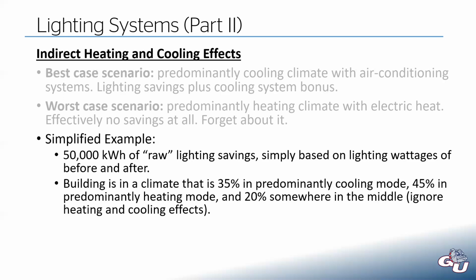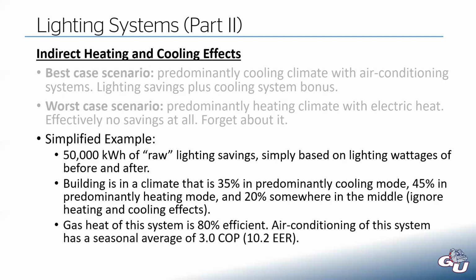And let's say this building is in a mixed climate where 35% of the time we are running our cooling systems, 45% of the time we're running heating systems, and 20% we're somewhere in the middle, and we'll ignore the heating and cooling effects in that middle ground. The HVAC at this building has a gas heating system that's 80% efficient. They have an air conditioner with a seasonal average of 3.0 COP, which is 10.2 EER. And they have utility rates of 9.2 cents per kilowatt hour and 76 cents per therm. So that's the setup.